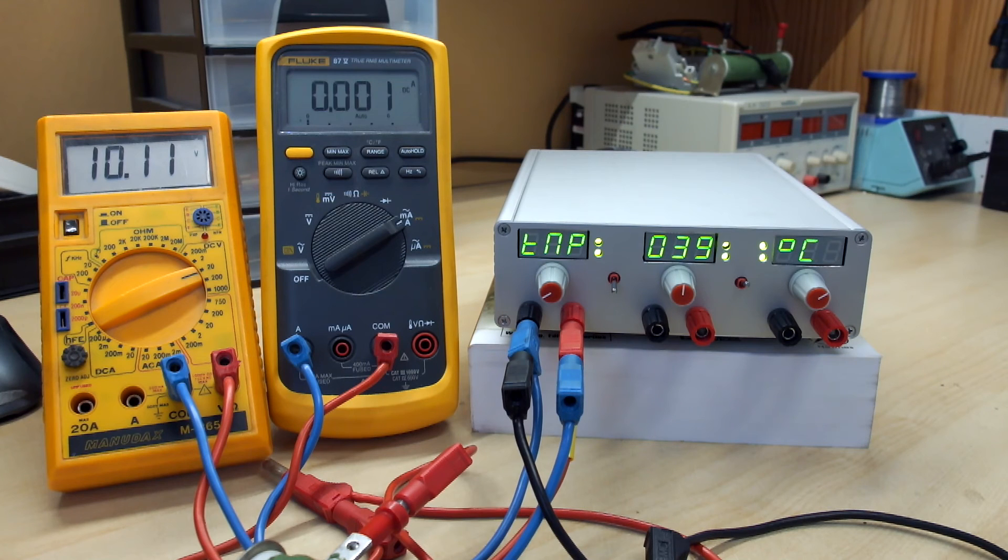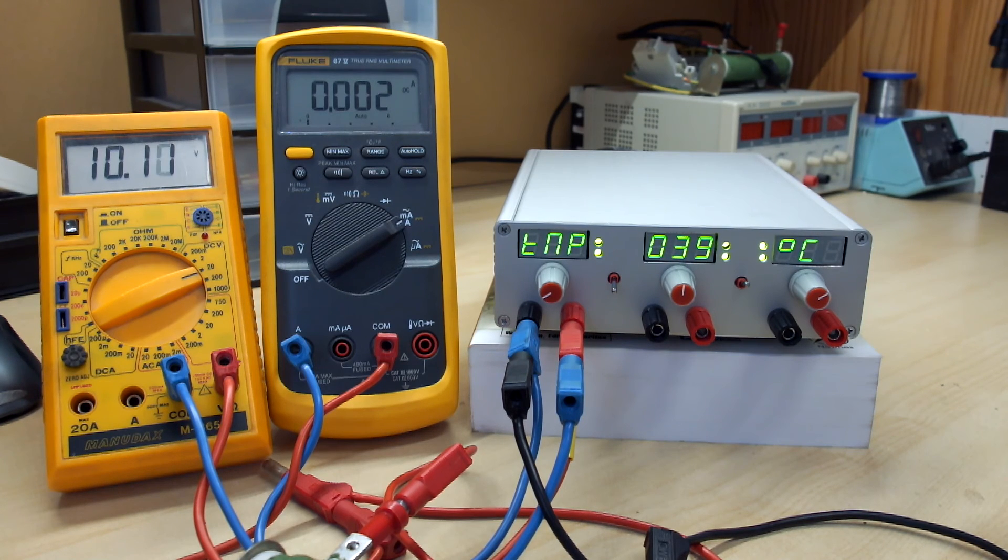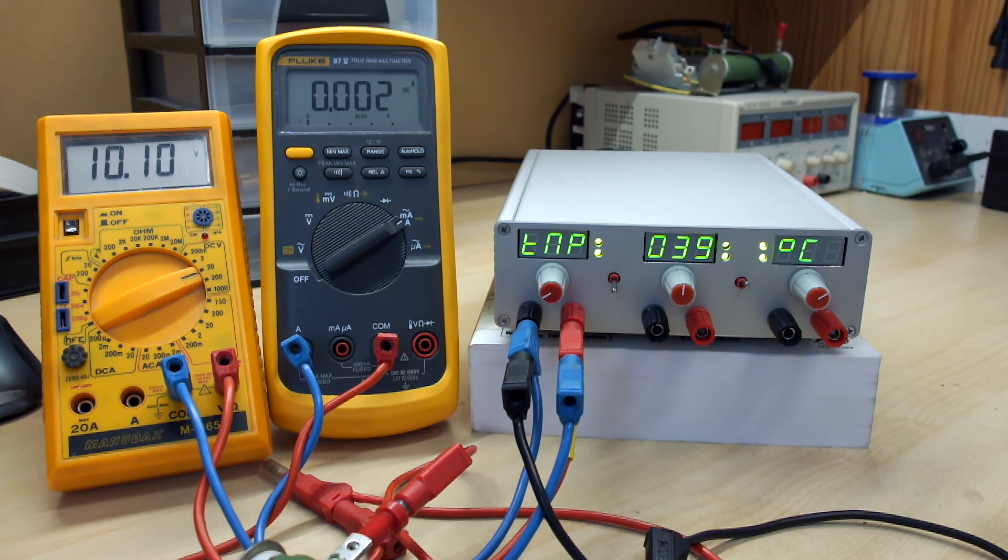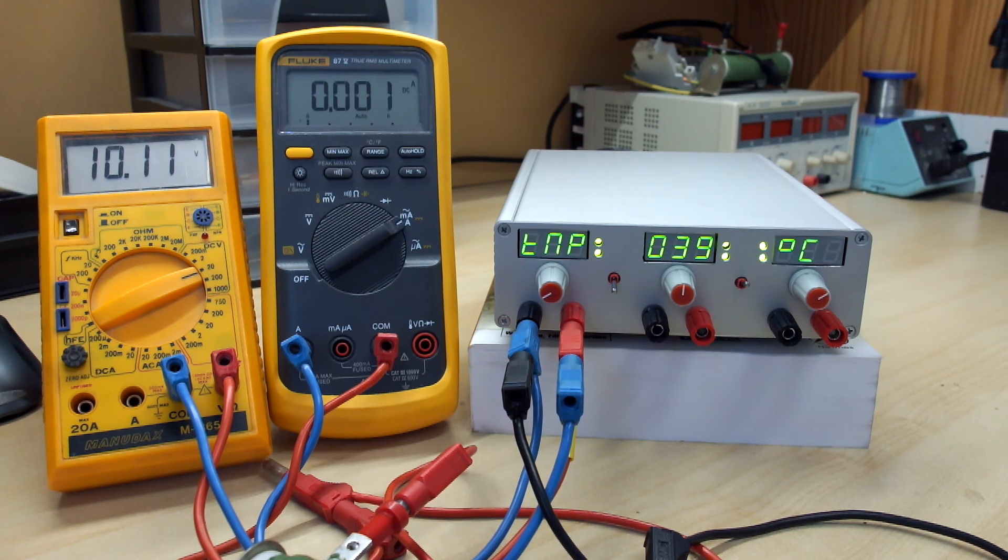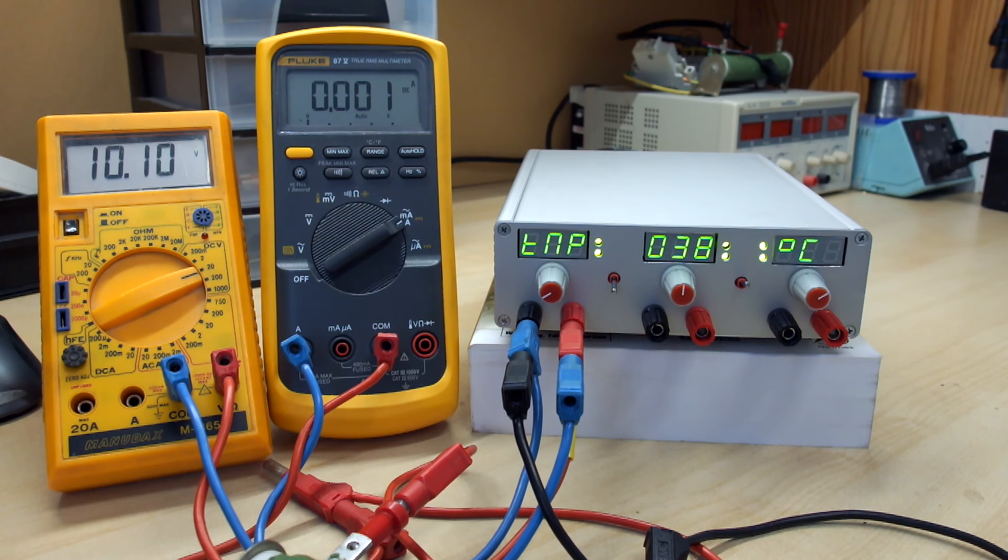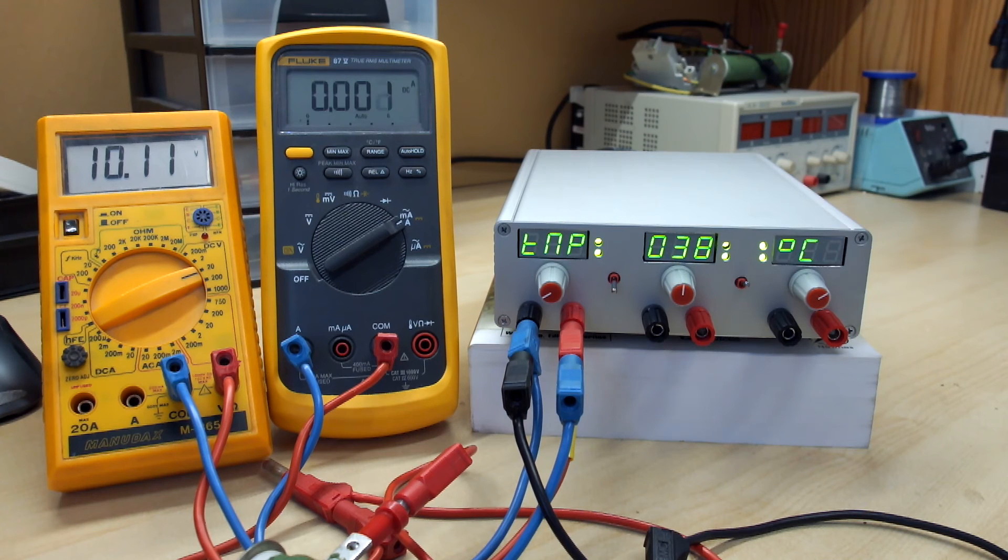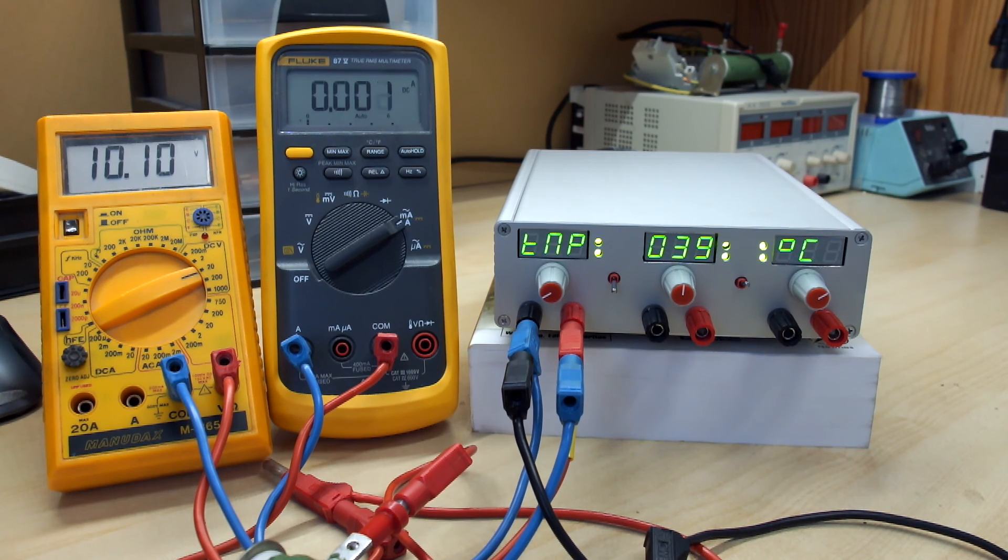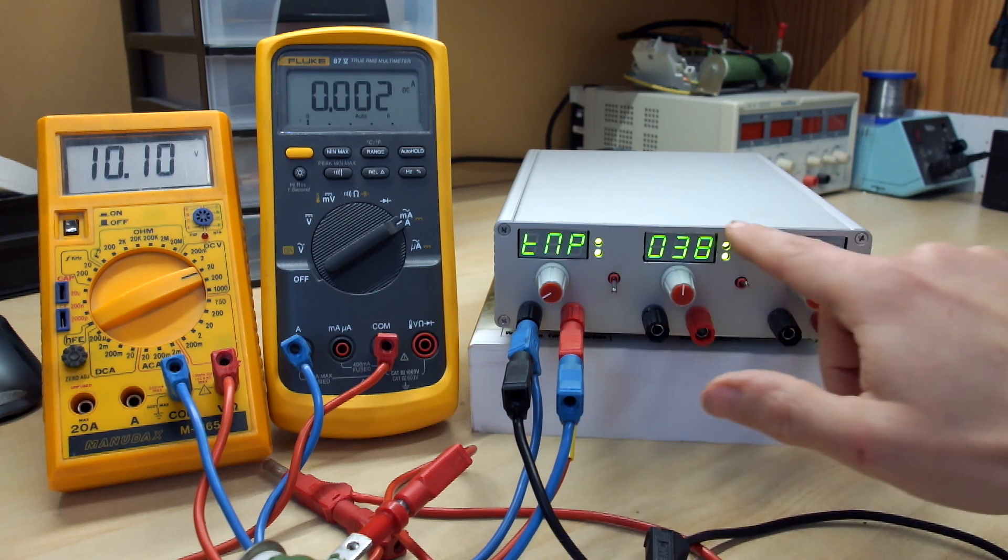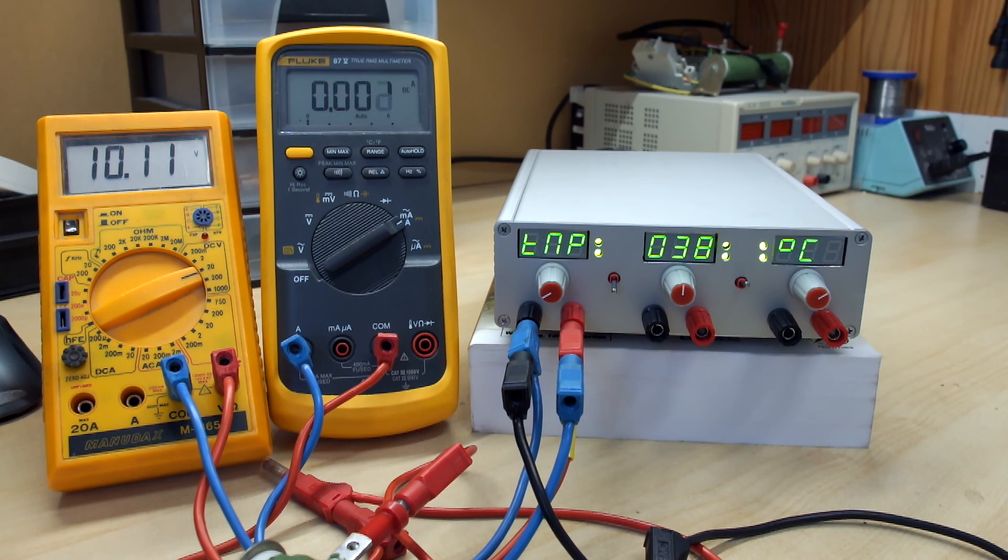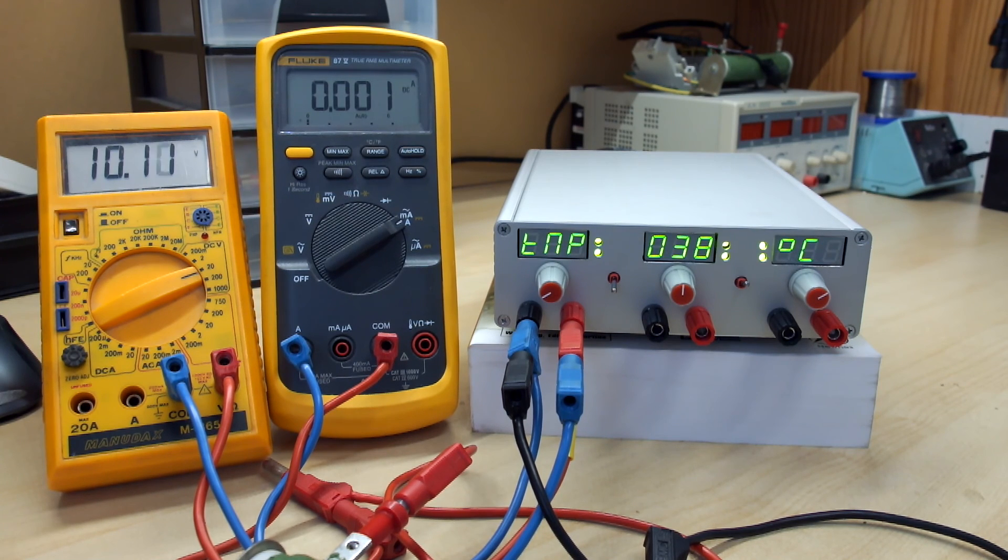So until the internal temperature is 40 degrees, the fan is not turning and from 40 to 60 degrees, the fan speed is controlled from 20% to 100% of its full speed. That allows no noise from the fan if you need very low power and noise is controlled by internal temperature. If the internal temperature rises up to 70 degrees, you have a thermal shutdown, all output is disabled and you have the LED, the upper LED becomes red, saying there is a thermal shutdown. And of course all outputs are disabled until the internal temperature is back to 50 degrees.